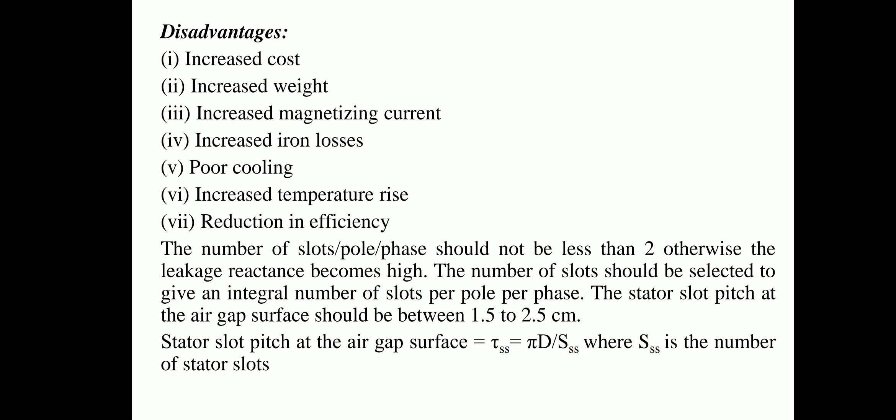The number of slots per pole per phase should not be less than two, otherwise leakage reactance becomes high. The number of slots should give an integral number of slots per pole per phase. The stator slot pitch at the air gap surface should be between 1.5 to 2.5 cm, given by: τss = πD / Sss, where Sss is the number of stator slots.